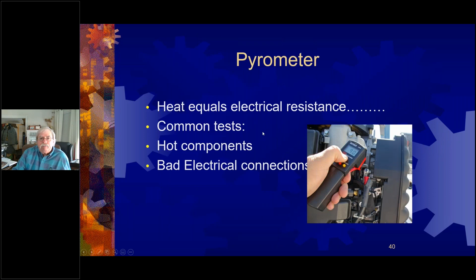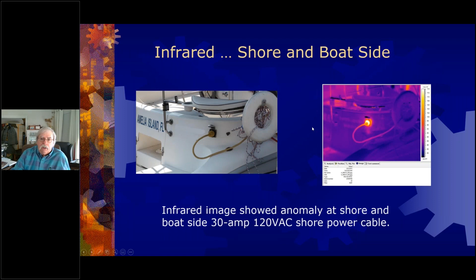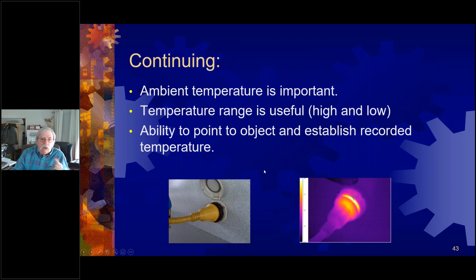The pyrometer, that, and you've got to be careful if you're going to get into thermal imaging. This particular boat had a legitimate problem, but notice how bright that connection is. That's an issue, but not really. You need to look at the temperatures and make sure you see what the variation is. I used to use a 25-degree Fahrenheit temperature spread as a clue that there's a problem. If the temperature at the bright point is 25 degrees Fahrenheit or more than the norm, there's a probable issue. Here's a good example of it.